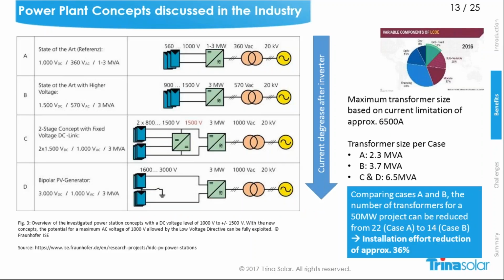What can be done else? Another idea is to work on the concept of the plant. That means on the inverter and transformer concept. Here are displayed 4 different cases. Case A is the known one with a 1000 volt system with an output voltage at the inverter side of approximately 360 volt. Then the increase to 1500 volts leads to an output voltage that can be increased to 570. The concepts C and D show further options with bipolar to further increase the output voltage.